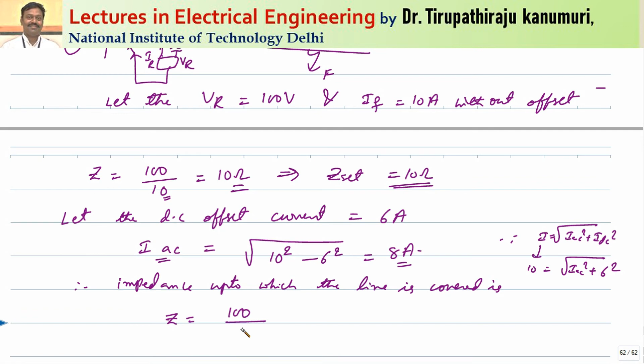So let us see the impedance up to which the line is covered. The voltage is 100 and the steady state value of the AC is only 8. So it will protect up to 12.5 ohms of line impedance. It is measuring up to 12.5 ohms of the line impedance, but actually it should only measure up to 10 ohms. It is protecting up to Z equal to 12.5 ohms for the given setting.